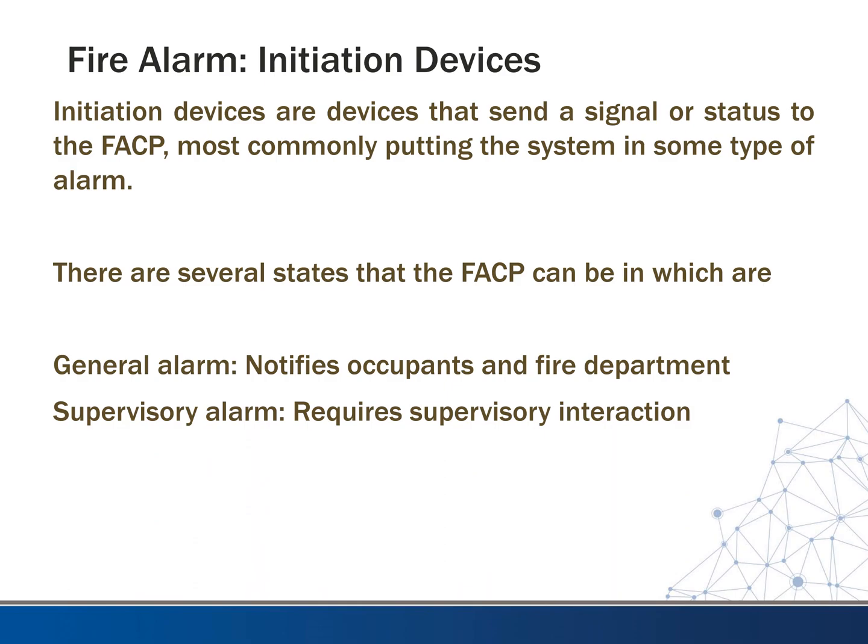You can have a supervisory alarm, which requires supervisory interaction and does not necessarily contact the fire department. An example of this is in hotels — we'll have smoke detectors throughout the facility and also in each guest room. The ones in the corridors, lobby, and common areas, if they detect smoke, will put the system in general alarm, meaning the life safety pathway is potentially obstructed by smoke or fire.